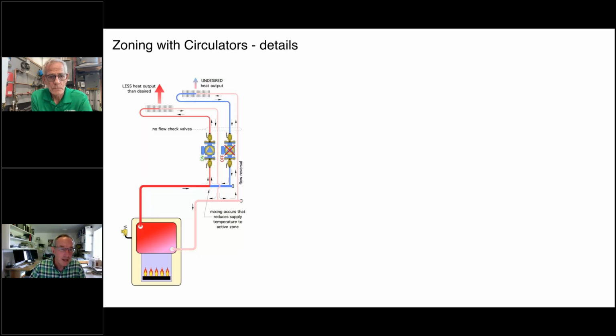It's going to flow through that circuit in reverse because there's nothing to prevent it. It's going to cool off to some degree, and then it's going to flow back, and it's actually going to mix with some of the hot water that has gone through the boiler. So that's doing two things, both of which are undesirable. One is you're reducing the supply temperature going to the zone that's active. It's not getting the full benefit of the temperature of the water coming from the heat source. And secondly, you're going to get some heat output, even though the flow is in reverse, in zones that don't need that heat. The thermostat isn't calling for heat.